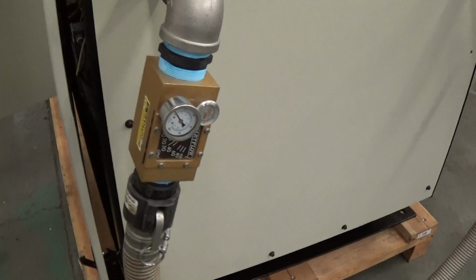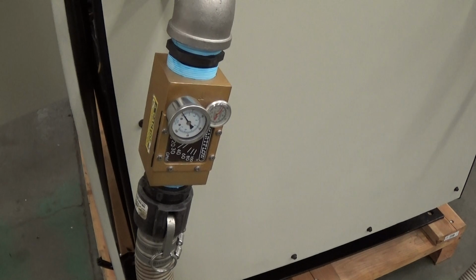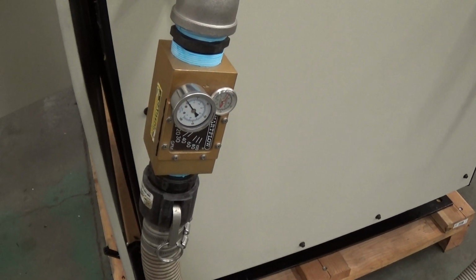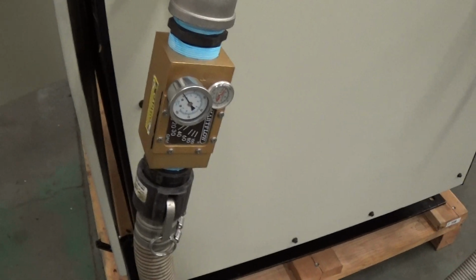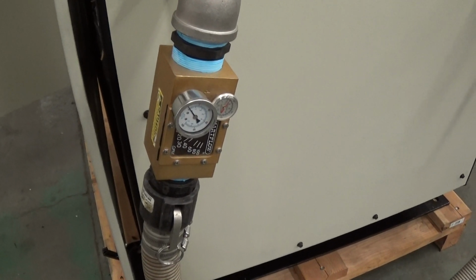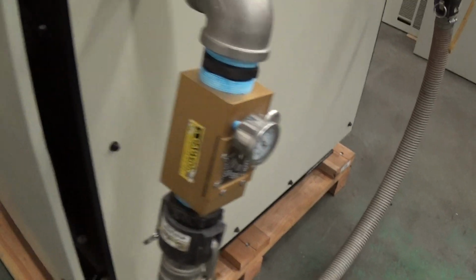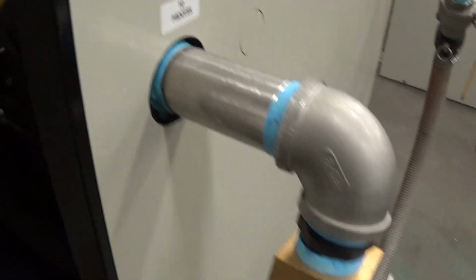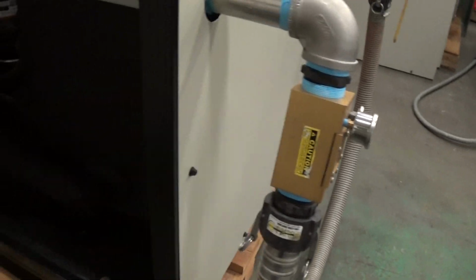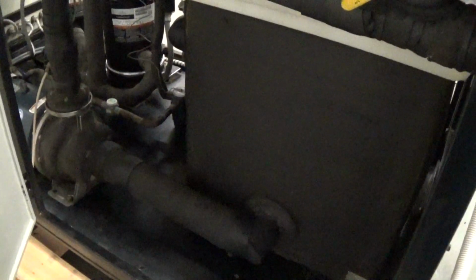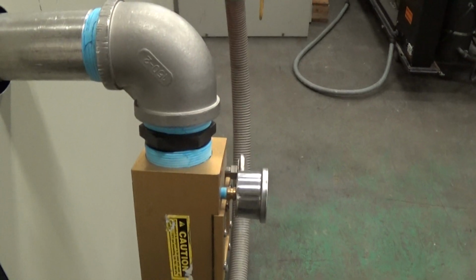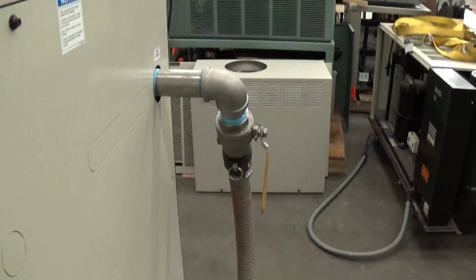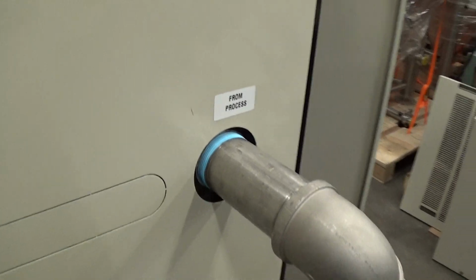We put on a GPM flow meter. In theory, for 20 tons of cooling, you like to see about 2.4 gallons per minute per ton. If you're going to be running colder temperatures, colder meaning below nominal, something below 45, 50 average temperature degrees, that 2.4 GPM per ton can be reduced 5, 10, 20%. This is your pump. It's suctioning off the reservoir tank. Then it pumps out to the process. It's going to go out to your process, then come back to the from process fitting here.